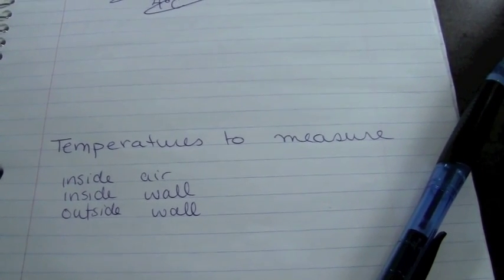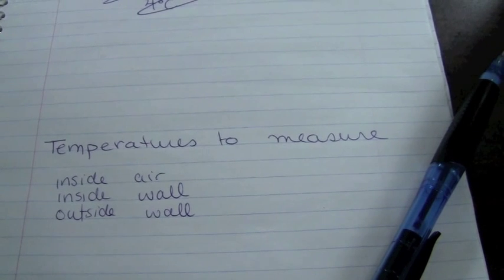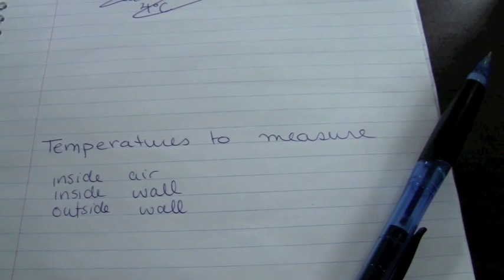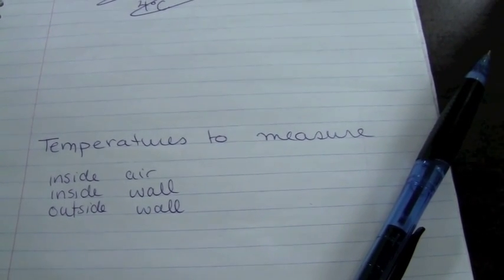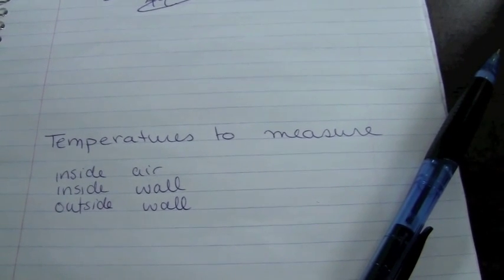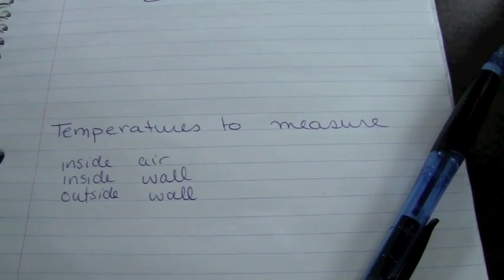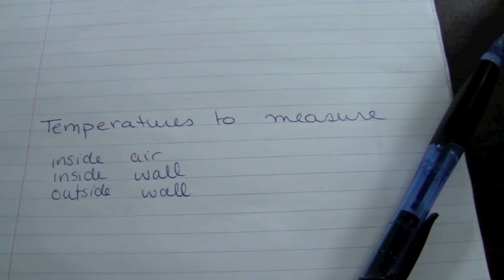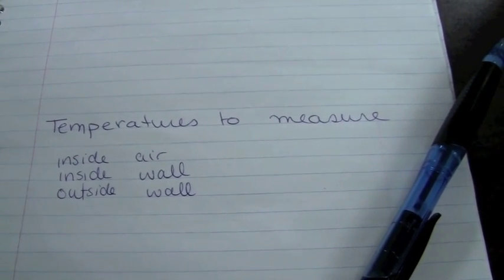Now, before we get started, there are a couple important things that you need to take note of. First of all, avoid taking these measurements when a surface is in any direct sunlight, and try to take multiple measurements along the same surface just in order to have values to compare to one another. These temperatures also need to be taken during the same time period, otherwise they won't be related to one another.